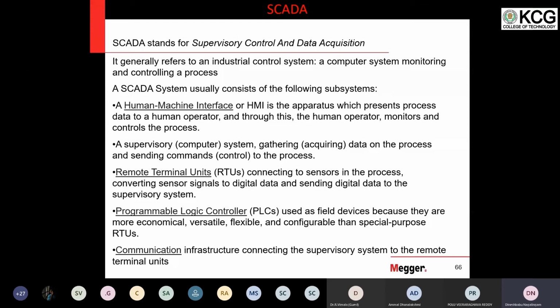If you just visualize your control panel now, we can very clearly see I am recording current, I am recording voltage, I am recording power. All these things we actually have in the control panel. That is eliminated and it is currently available in our system. That means we are acquiring data. Next is supervisory control. You can supervise the status of isolator and breaker. You can control the isolator and breaker. If you are able to do all these things in one single computer, it's called SCADA: supervise, control, and acquire data.